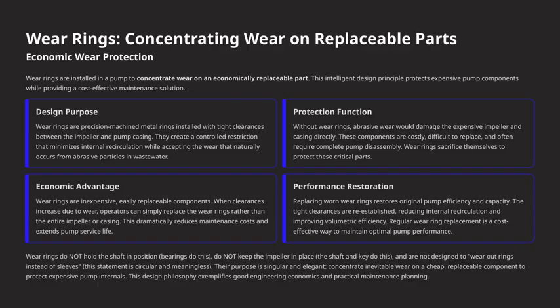They are carefully machined metal rings installed with tight clearances between the impeller and the pump casing. Their role is to create a controlled restriction that reduces internal recirculation, and they accept the wear that naturally occurs from abrasive particles in wastewater. Without these wear rings, abrasive wear would directly damage the impeller and casing. Since these parts are costly and difficult to replace, often requiring a complete disassembly, they need this sacrificial component to take the brunt of the wear.